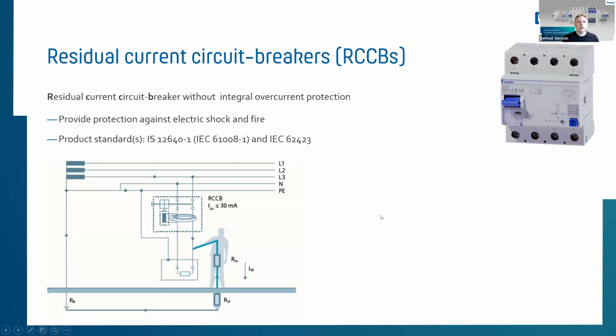As in the first introduction by Mr. Kumar and also Krish, we are talking about devices detecting whether a fault current in a system, in a three-phase system, is unequal to zero. All the currents going into a circuit and coming out of it have to sum to zero, and the RCCB measures this value. If it's not zero, the RCCB will trip at a certain value. It's an electromechanical device, and it protects against electric shock and fire.